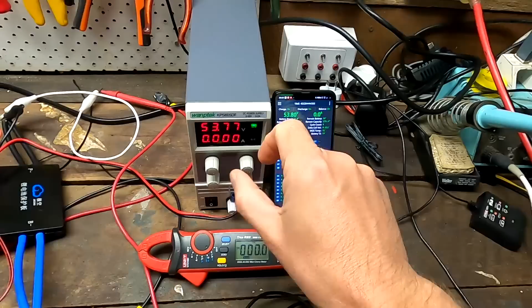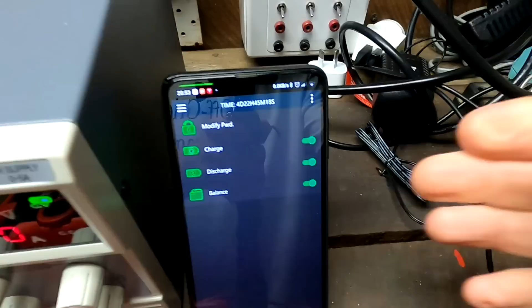But only if discharge is disabled. Under normal conditions, you have both switches on, of course. In your app, you have both switches turned on, charge and discharge. It is very, very unlikely that one of the switches is turned off manually. This is only for testing purposes, so I will use this quite often, actually. Or if you do maintenance or for any particular reason you want to disable charging or discharging with your BMS from your battery.